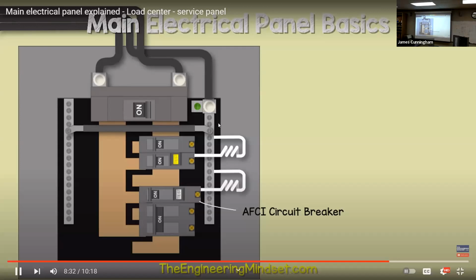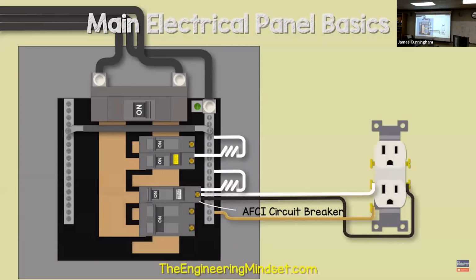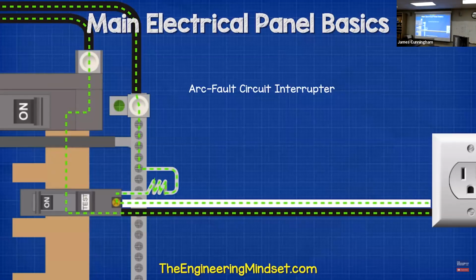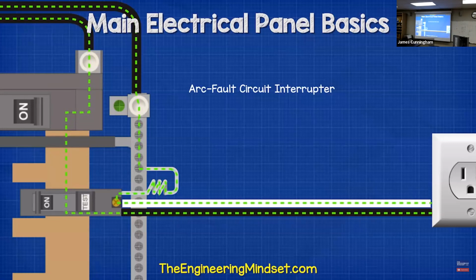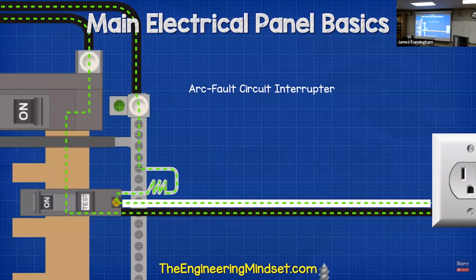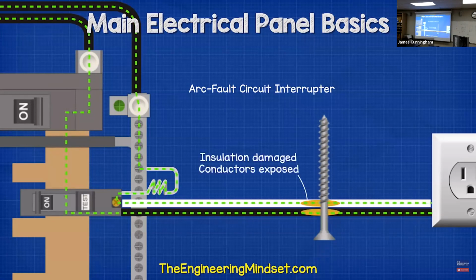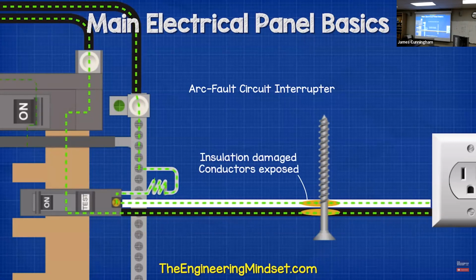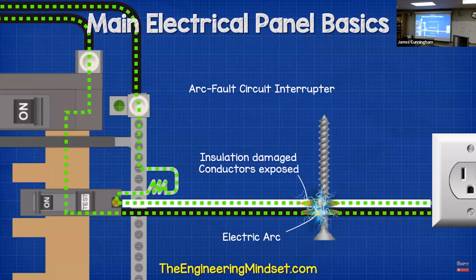AFCIs work also by being connected to both the hot and neutral wires. Inside this circuit breaker is a circuit board which is measuring the circuit and monitoring for patterns which indicate an arc fault is occurring. These are installed pretty much identically to how we saw the GFCI breaker. Under normal conditions, the current flows through the hot, back through the neutral into the breaker, then through the pigtail and back through the neutral bar. But if, for example, a screw was accidentally inserted very close to the cable and removed the insulation to expose the copper wires, the electricity could now potentially jump across, or arc, from the hot wire into the neutral.